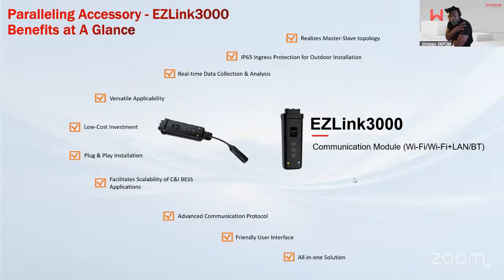Now it's time for me to talk about the EZLink 3000, which is the only accessory we have for easily linking inverters, as the name says. This accessory will allow mostly our hybrid inverter to be linked in parallel. The newer generation string inverter can also be used with the EZLink, but mostly this device has been created for the hybrid inverter, ESG2 on the single phase, ET and ETG2 on the 3-phase.